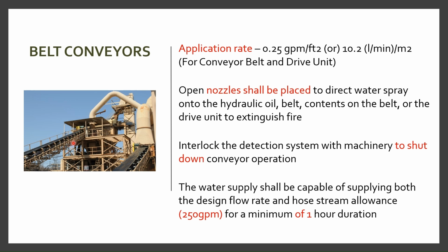So top and bottom should be protected by using open spray nozzles, and these nozzles shall be placed to direct water spray onto the hydraulic oil, belt, contents on the belt or the drive unit to extinguish fire. And also, if you have worked on some projects, you will understand this material through the belt conveyors will go to other buildings as well. If the fire occurs at this particular location, the burning material should not reach the other building. That's the reason we need to protect that building as well.